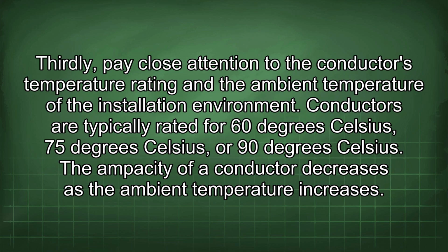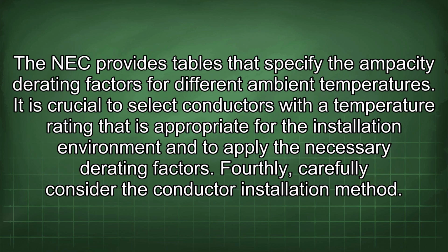Thirdly, pay close attention to the conductor's temperature rating and the ambient temperature of the installation environment. Conductors are typically rated for 60 degrees Celsius, 75 degrees Celsius, or 90 degrees Celsius. The ampacity of a conductor decreases as the ambient temperature increases. The NEC provides tables that specify the ampacity derating factors for different ambient temperatures.